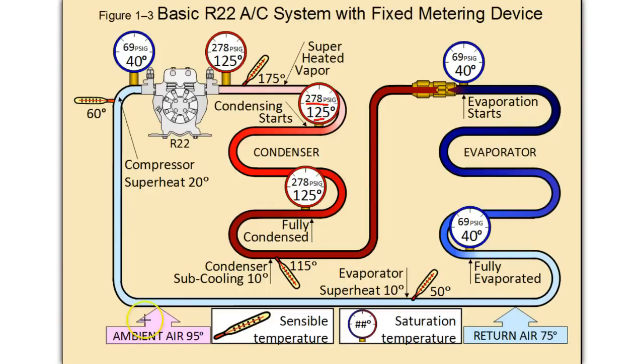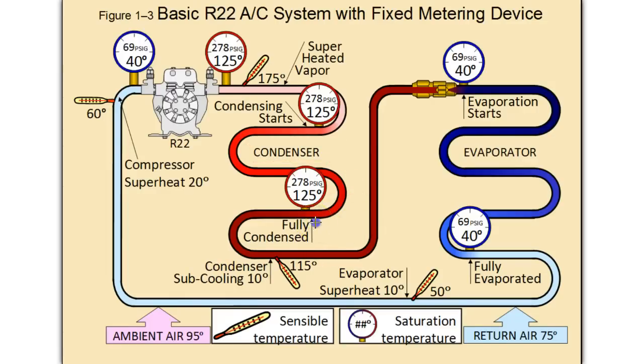As the saturated refrigerant moves through the condenser it begins to condense more and more — at this point it could be 75% liquid and 25% vapor, still at its saturation point. It will travel through the condensing unit until it hits the point where it is fully condensed, meaning 100% liquid with no more vapor. The region between where condensing starts and where the refrigerant is fully condensed is where all of the latent heat is shed as it changes state from vapor to liquid.